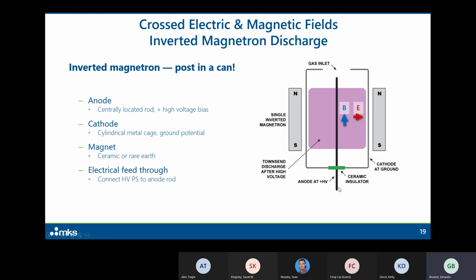We have an anode in the center. This is a cylindrical symmetry chamber. That anode gets biased to positive high voltage. We have a cathode at ground. So when I bias this anode, I get a radial electric field. We also have a magnetic field, which is a cylindrical magnet in this case, that is axial. So we have a crossed magnetic and electric field. And when we apply high voltage to the anode, a discharge is established. It's called a Townsend discharge. And the discharge current that flows through this chamber is the measurement of the pressure in the system. That's how cold cathode gauges work.